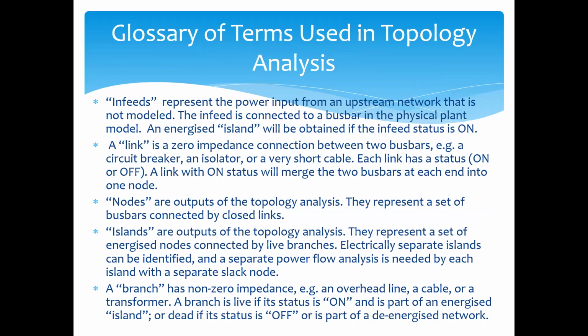There are specific terms used in a topology analysis. In-feed. In-feed represents the power input from an upstream network that is not modeled. For example, we are not going to model the transmission network in a distribution system study, so we represent it by an in-feed, that means power input from upstream. If the in-feed is connected to a bus bar in the physical plant model, an energized island will be obtained if the in-feed status is on. If the in-feed is on, we can identify an island which is energized. If the in-feed status is off, it is de-energized.